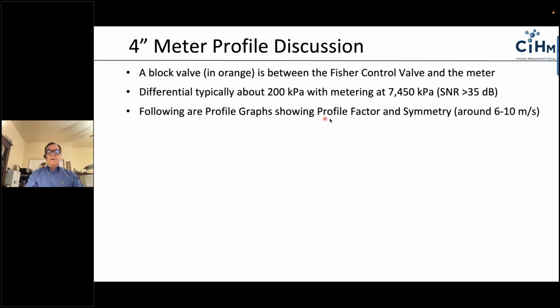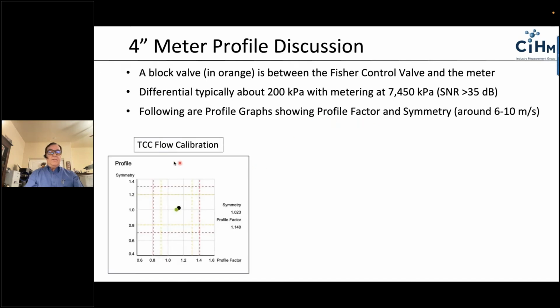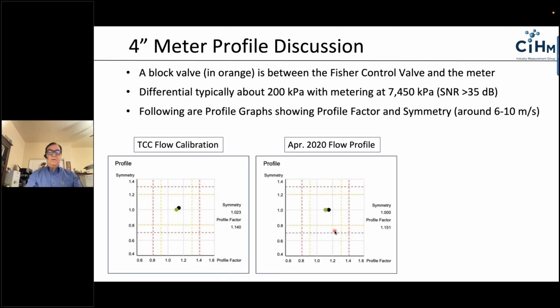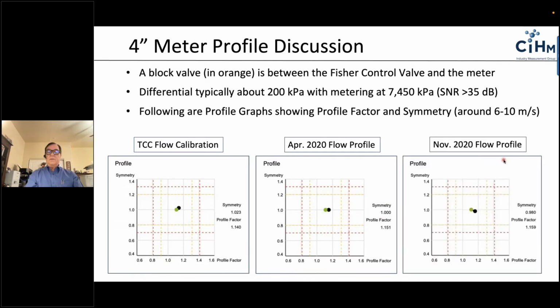The following profile graphs talk a little bit about what the profile looks like coming into the meter. At the time of calibration on this meter, we can see the profile indication, symmetry on the y-axis and profile factor on the x-axis. The installation in the field in April looked like this, very similar symmetry and profile factor. After about 7 months, the profile factor is very close to the initial installed. So we've had liquids go through the meter during this period of time. The symmetry and the profile factor, once again, are very close to the initial startup condition, and they're also very close to the TransCanada situation.